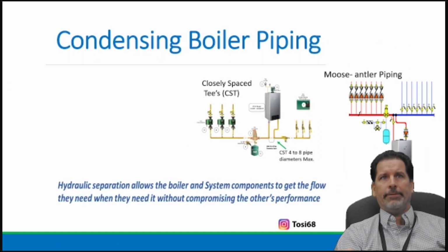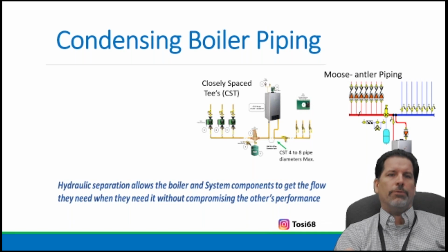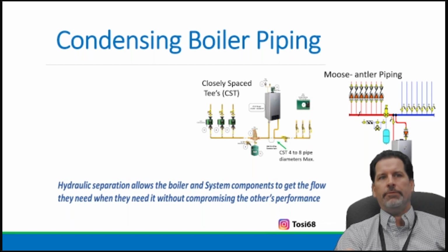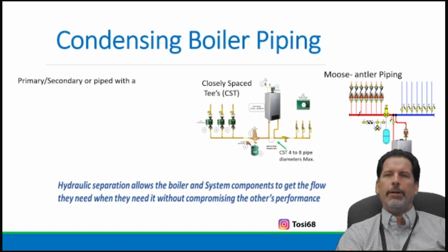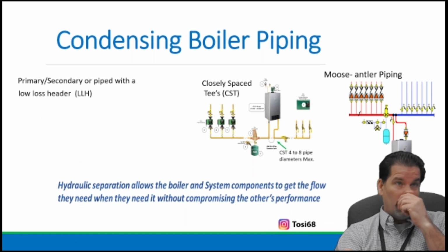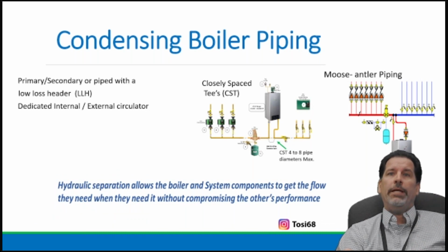So condensing piping, right? Boiler piping. This is starting now to build after we already derived what I need for the rooms and what I need for the whole home. And now I'm going to start from the boiler out. I make a selection. I have the boiler now. Now I need to set it up. It's unique. It's not the average of what we've done over 100 years of boilers, right? It's unique because it's primary-secondary piping, with a low loss header or something that's going to be decoupling the boiler from the system.